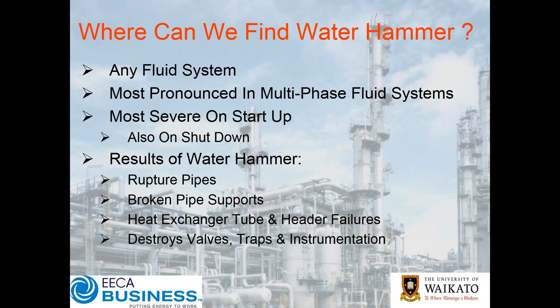What's the result of water hammer? Ultimately you'll have ruptured pipes — and when you've got a ruptured pipe, it's a little bit late. What often preempts that is broken pipe supports. As you wander around factories, you'll see pipe supports that have cracking or signs of wear, then you'll see them completely disconnected and pipes jumping around. Left unchecked, that's only going to result in further damage. If you leave it longer and longer, ultimately the equipment tends to decide for you that it's had enough — and generally, as I've said numerous times, equipment makes that decision at 2am on a Sunday morning as opposed to 11 o'clock on a Tuesday.